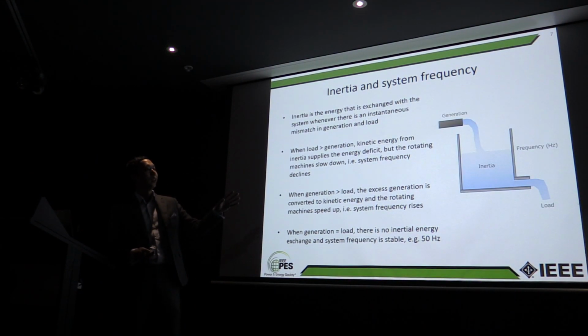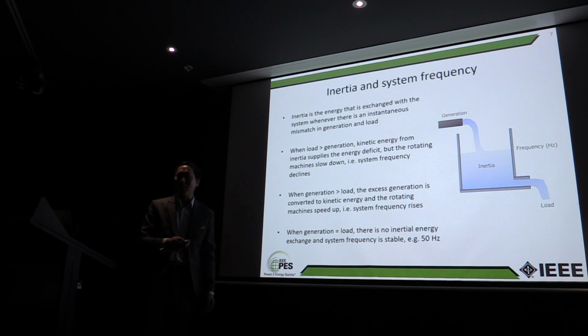This is the classical analogy for inertia, which is a tank of water, where the inertia is basically all the water in the tank. You have a hose with generation filling it up with water, and you have a tap with load, with water coming out. And it represents the frequency, the water level. So if your generation and your load are absolutely matched, you've got enough water coming in and the same amount of water coming out, then your frequency is going to just stay as it is. Should point out that load is net of losses as well, so it includes losses in the system.